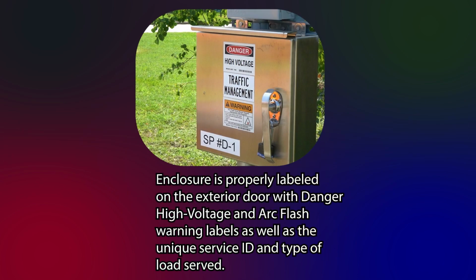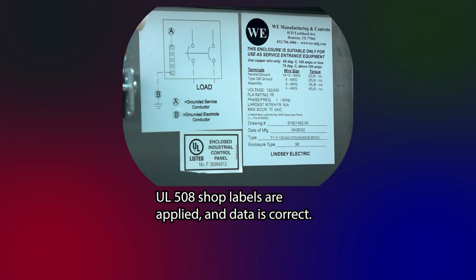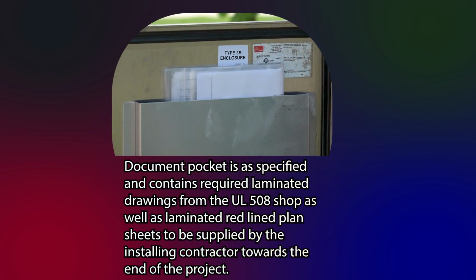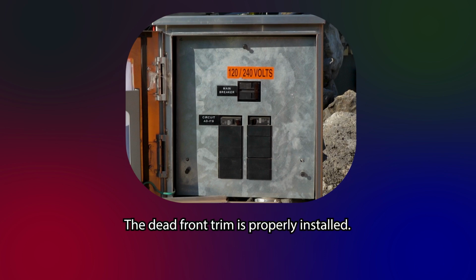Enclosure is properly labeled on the exterior door. The danger, high voltage, and arc flash warning labels, as well as the unique service ID and type of load served. UL 508 shop labels are applied and data is correct. Document pocket is as specified and contains required laminated drawings from the UL 508 shop, as well as laminated red-lined plan sheets to be supplied by the installing contractor towards the end of the project. The dead front trim is properly installed.